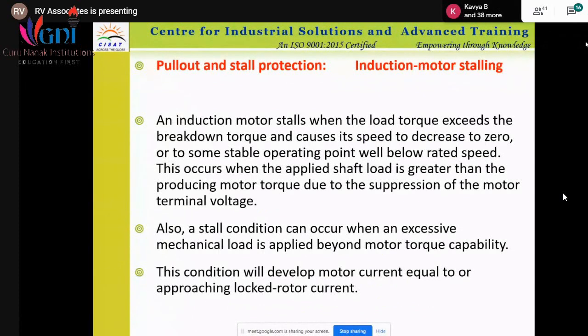Then pull-out and stall protection in case of an induction motor. So we know all those reasons. There is a starting zone, a breakdown zone, and a stopping zone in case of a motor. We say it's like acceleration and deceleration. Then there is dynamic starting and steady state starting. So all these concepts are required.